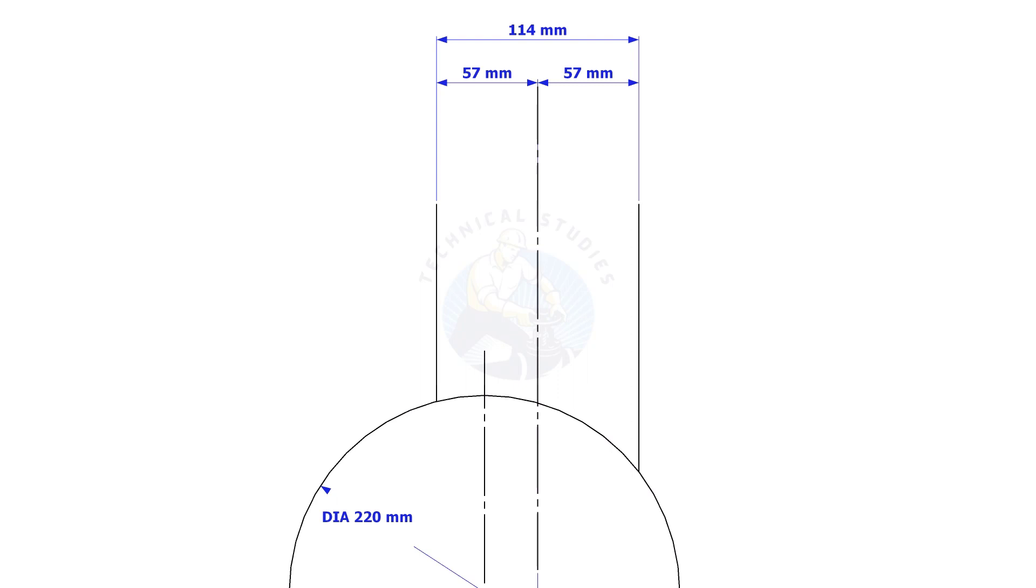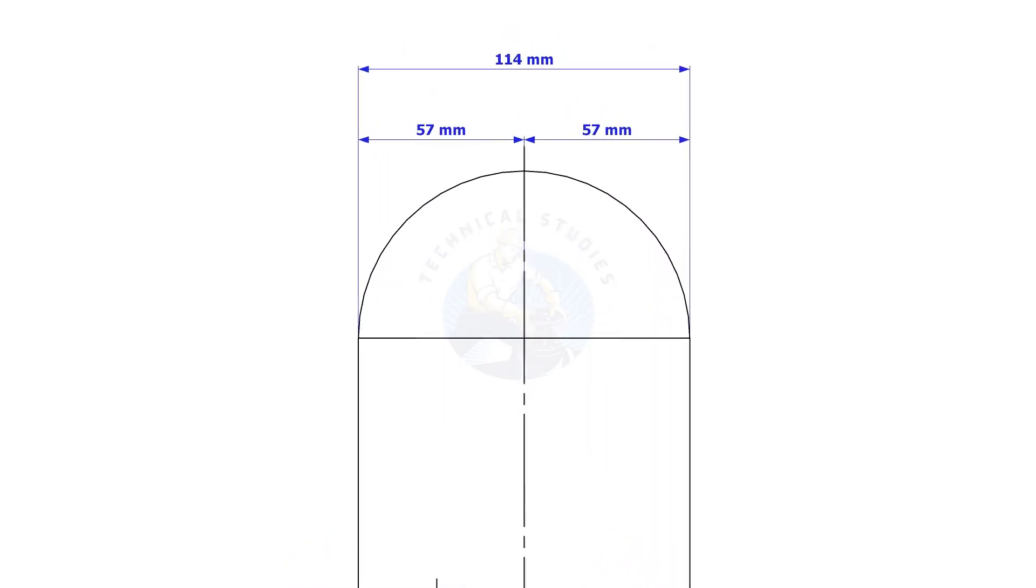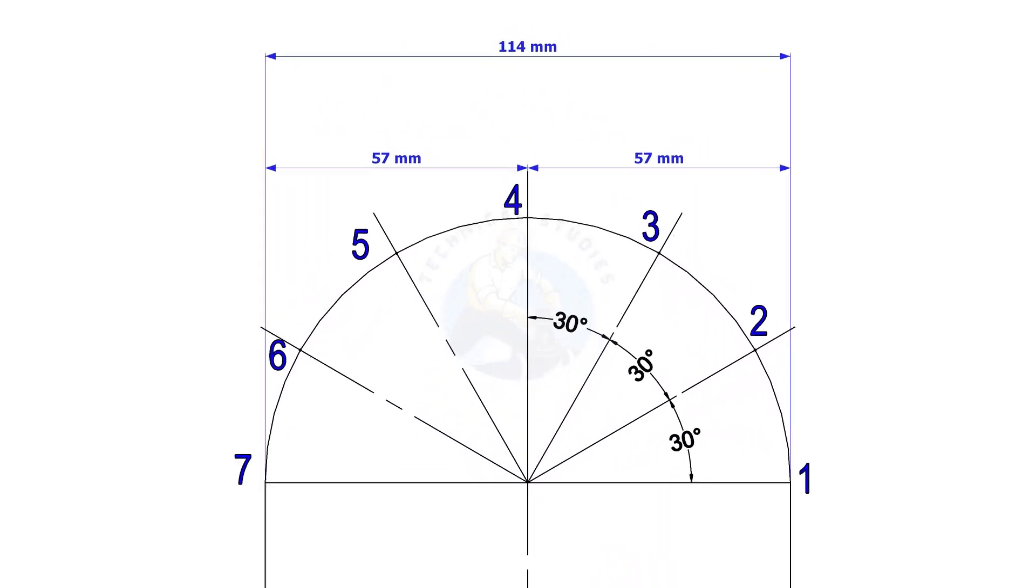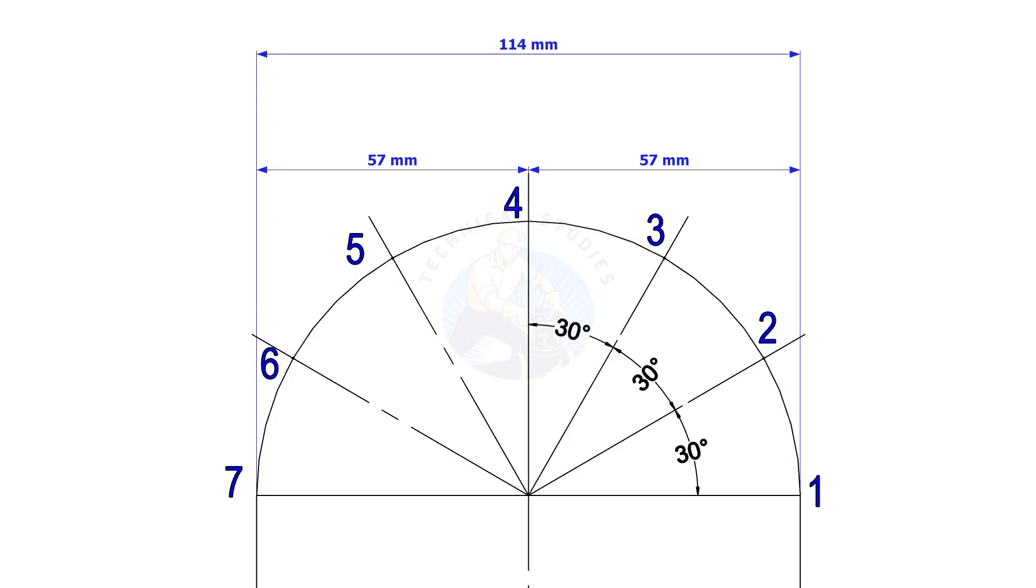Draw a half circle of radius half OD of the branch. Divide this half circle into six equal segments. If the pipes are above six inches, you may need to increase the segments for better accuracy.